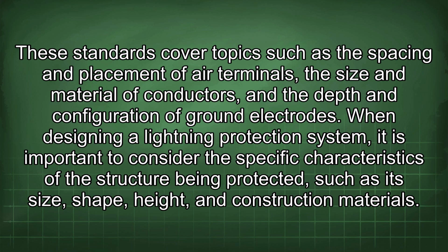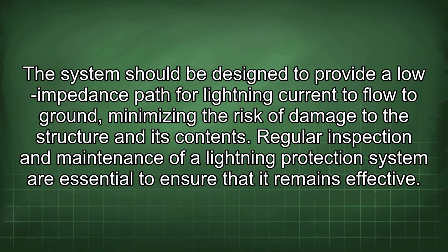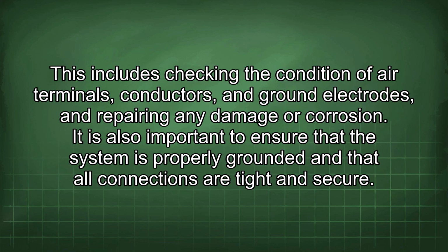When designing a lightning protection system, it is important to consider the specific characteristics of the structure being protected, such as its size, shape, height, and construction materials. The system should be designed to provide a low impedance path for lightning current to flow to ground, minimizing the risk of damage to the structure and its contents. Regular inspection and maintenance of a lightning protection system are essential to ensure that it remains effective. This includes checking the condition of air terminals, conductors, and ground electrodes, and repairing any damage or corrosion. It is also important to ensure that the system is properly grounded and that all connections are tight and secure.